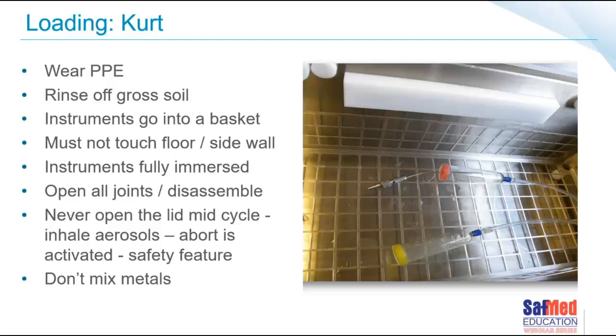So somebody forgot to put the basket back in. 100%. A lot of times we forget to put the basket back in, or we put something that's too big for the basket, and we're like, hey, let's move the basket out and put the instrument straight into the bath. You damage the ultrasonic bath, the floor. You also damage the instrument because it shifts around, and it will create little hairline cracks in the ultrasonic itself. But then we mentioned not touching the floor.